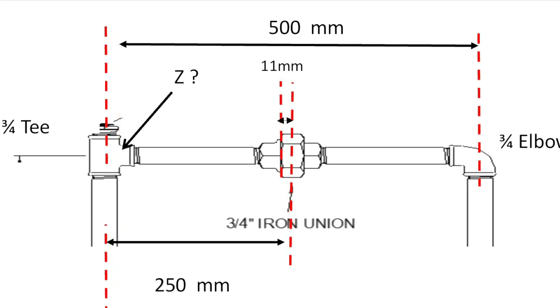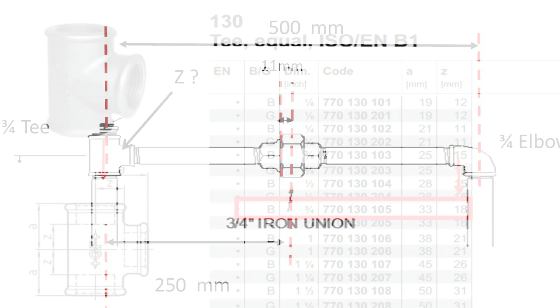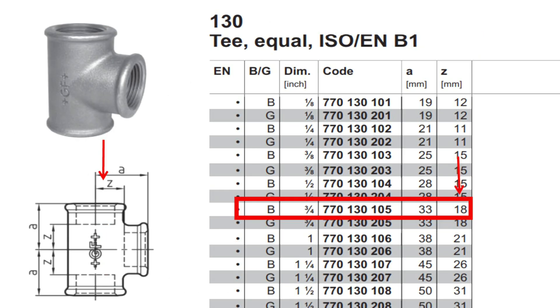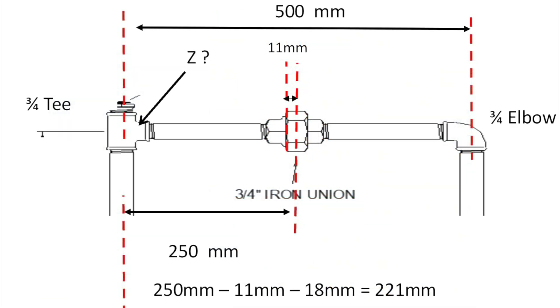Now let's work out the Z dimension for the T, which is 18mm. Right, so the Z dimension is 18mm for the T. Right, so what we do, just to recap, is 250mm, take away 11mm, which is half the Z dimension for the union, take away 18mm, which is the Z dimension for the T, gives us 221mm.